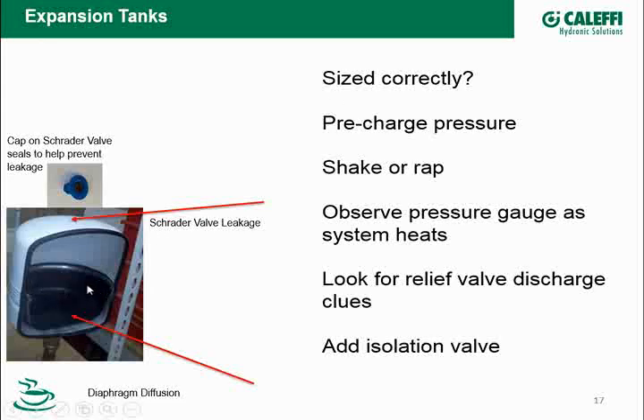This is a cutaway of a typical what we call a diaphragm tank, and the way this works is you can see there's a little Schrader valve at the top that you put the air charge in there, and then there's a bladder, and it's basically crimped. You can see this one little connection right here, so this little membrane is crimped in there, so there's air on one side and, of course, the fluid on the other, and it pushes up and down.